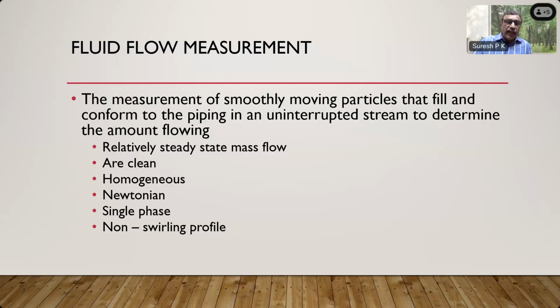The fluid is clean, because for many of the flow meters the clearances are very low, or the tube size is very small, or the pressure loss becomes more if it is not clean. All these things are problematic for an actual, accurate flow measurement. Then the flow is homogeneous. Heterogeneous flow is very difficult to measure.